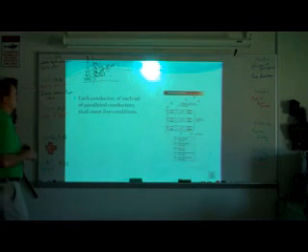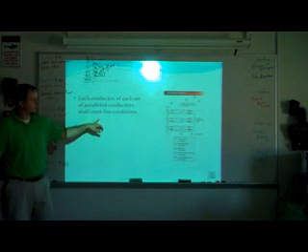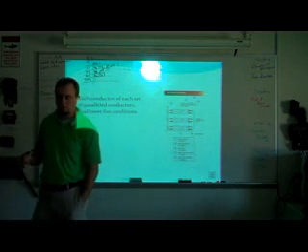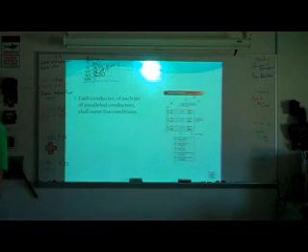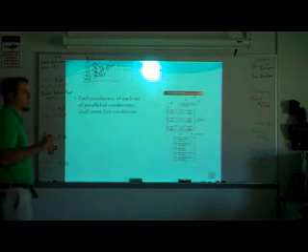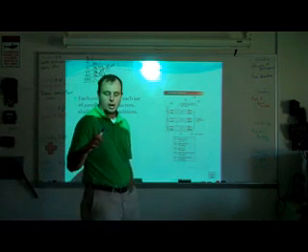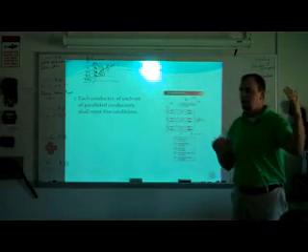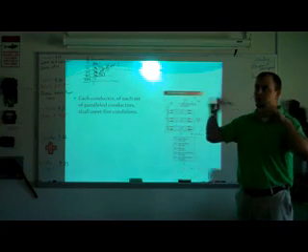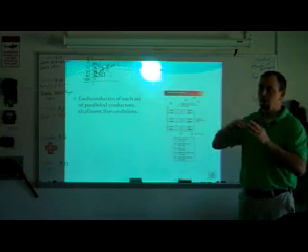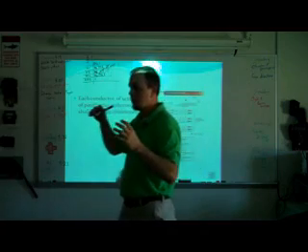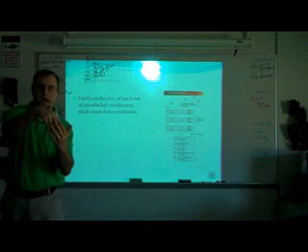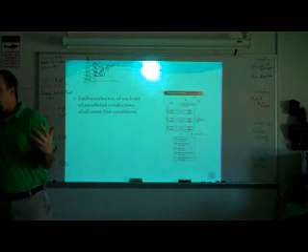Each conductor of each set of parallel conductors shall meet 5 conditions. Okay? So you'll go through here and it'll talk about the 5 conditions for using parallel conductors. And you'll use parallel conductors whenever you want to share a load. Like if you have a very large service coming in and you want to share it between 2 different panels, you're going to parallel the wires. You're not going to go into the panel and come out of a circuit breaker. You're going to come into the top, right back out of the top, and over to the next panel.